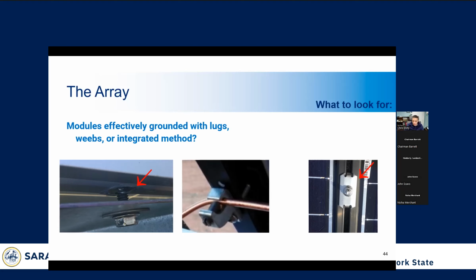Many times these are installed on roofs. So if you think about, for instance, a mason climbing on a roof to fix your chimney, and if they just accidentally touch one of the panels, they could receive a shock of up to 600 volts DC or more. And that can be prevented by careful grounding and bonding. And so there are traditional ways of bonding, which you would see like with a ground lug and a copper wire. That's what you would more likely see in older installations. A lot of times now they're going more towards integrated bonding, which you can see an example of here.